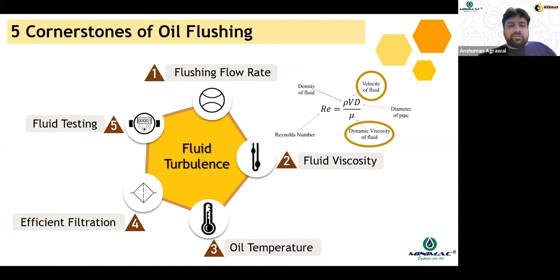Now let's go into the depth of each of them. The first one is flushing flow rate. As we understood, turbulent flow is required, and for turbulent flow you need a Reynolds number of 4,000 or above. Now, in order to decide this flow rate, as we also talked about in one of the myths, you don't take the largest pipeline diameter, but you actually take care of each of the branch lines. So here we have a small diagram which can give you an understanding of how the importance of branch lines plays into flushing flow rates.